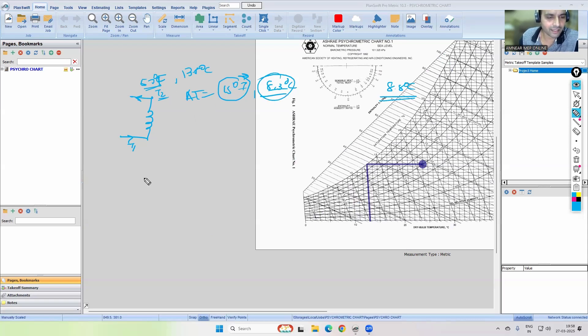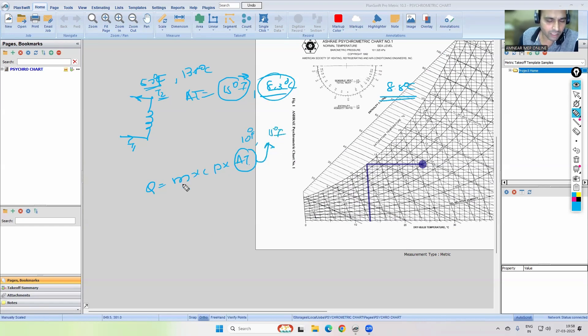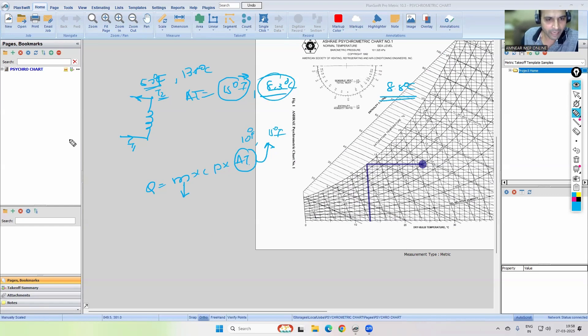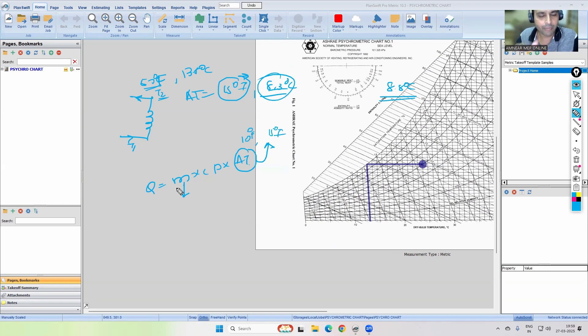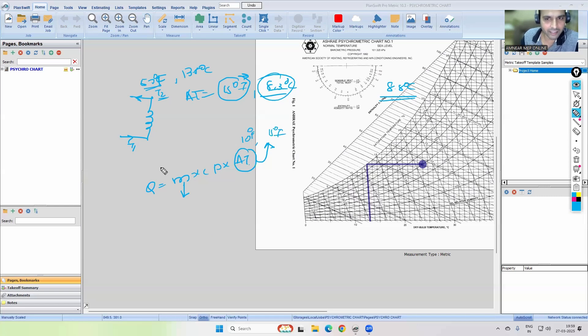Why are they increasing the delta T? Consider Q = M × Cp × ΔT. Before, delta T was 10°F; now if you consider 15°F, delta T increases, so mass flow rate M decreases. Decreasing chilled water flow rate means the pipe diameter decreases, reducing initial investment in piping. Also, pump flow rate decreases, so pump capacity decreases, and the electrical energy consumption of chilled water pumps within the closed loop decreases. So we can save energy, making it an energy-efficient optimized selection. That's why standards recommend higher delta T.